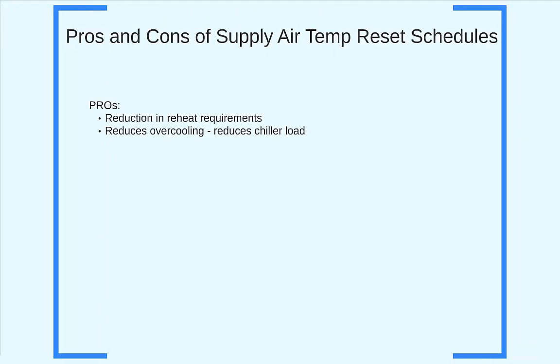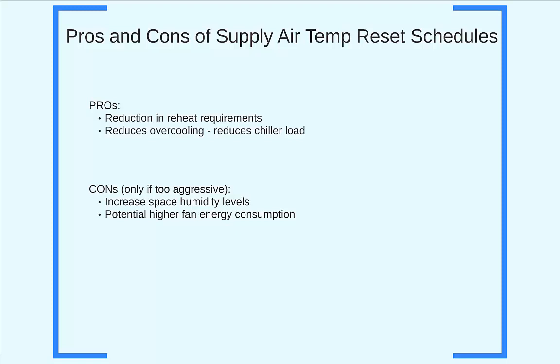So to sum it up, here are the pros and cons of supply temperature reset schedules. Pros include a reduction in reheat requirements. It also reduces overcooling the space, which effectively reduces the load back at the chiller. The cons come from when we program in too aggressive of these schedules. They include increased space humidity levels, as we just saw, and a potential for higher fan energy consumption.